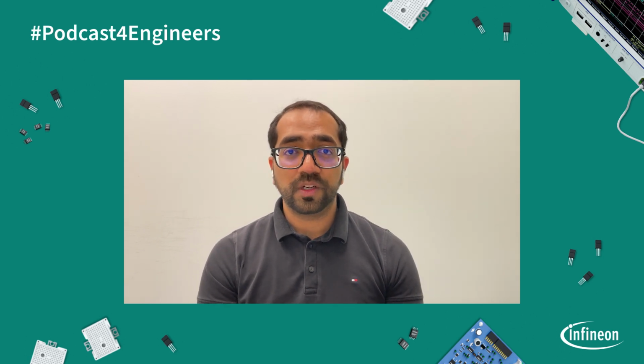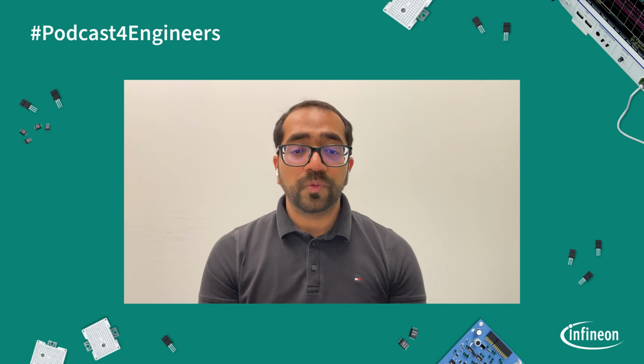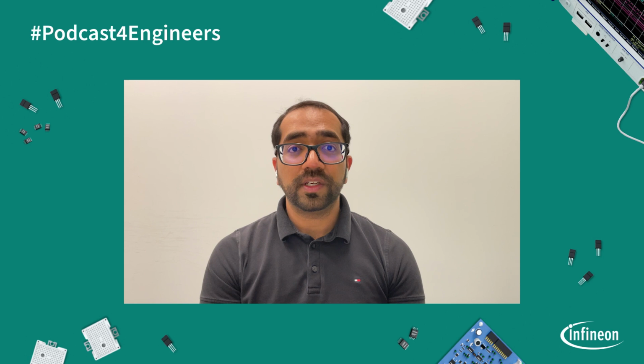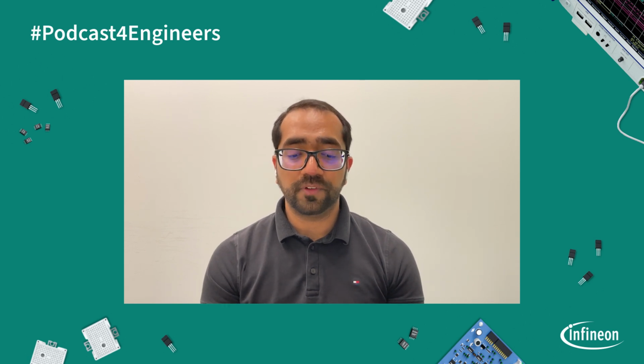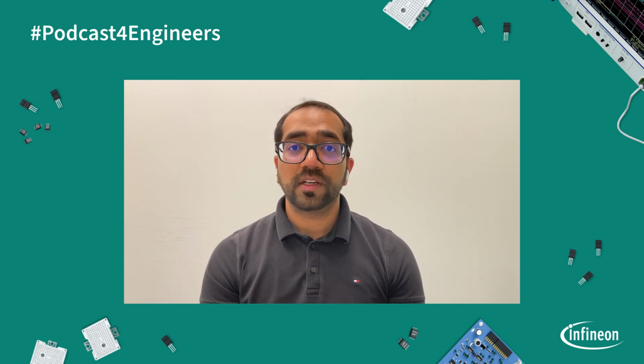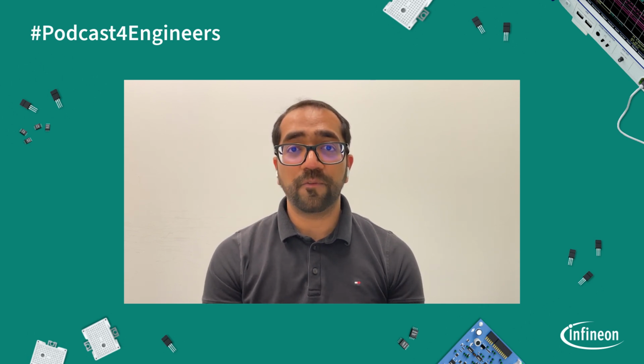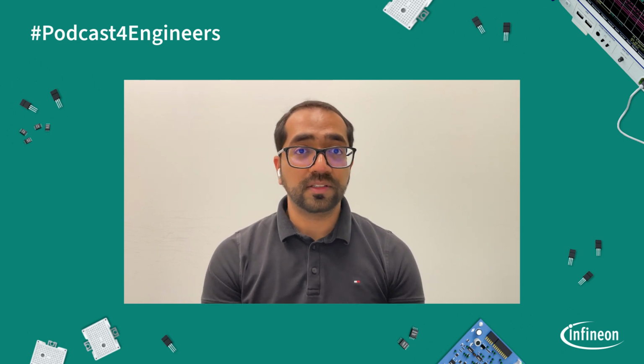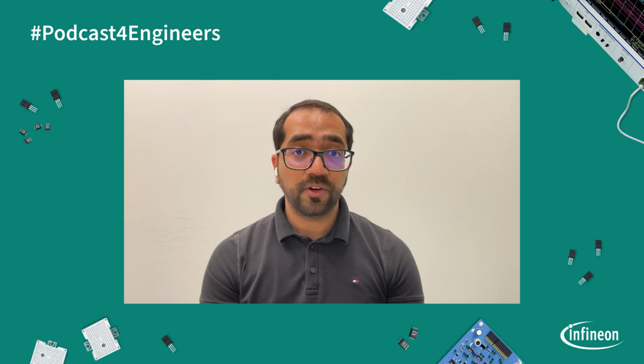If we go back to our 12-volt architecture, that's how it started, and then it switched to something called an eFuse, an integrated solution. We are seeing the same trend in the 48-volt backplane, where the industry is looking for an integrated solution that integrates the controller, the MOSFET, the current sense shunt, and the temperature sensor into one package. It will improve the power density. Plus, this will be a stackable solution. Let's say you have one eFuse of 20 or 30 amps, which can do 1 kilowatt of power. If you need 2 kilowatt of power, you can just tap two in parallel, three in parallel. That's the trend right now.